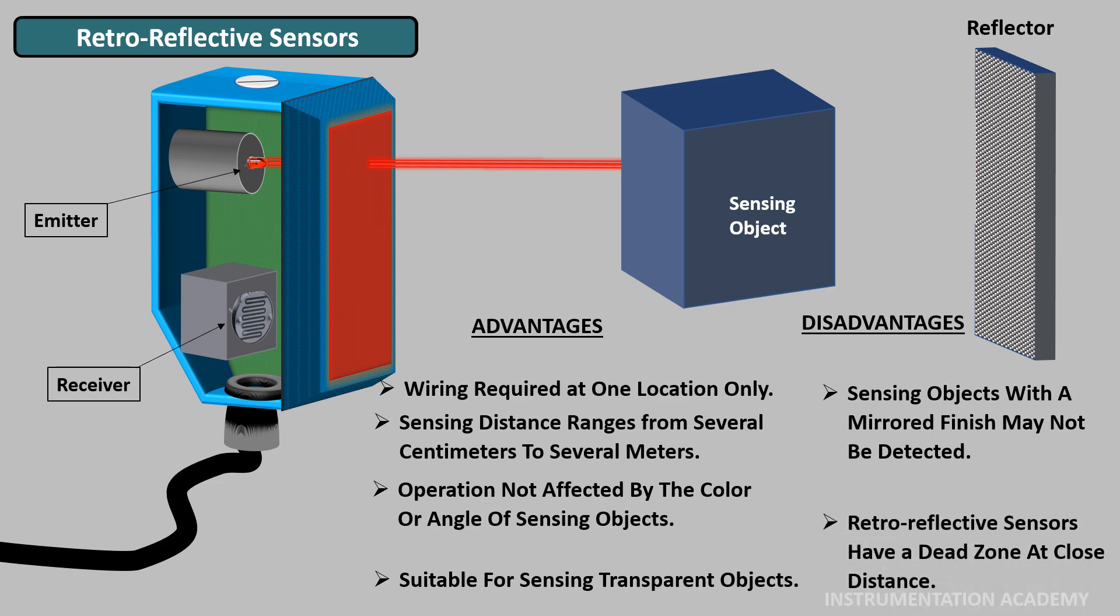Disadvantages of retro reflective sensors: Sensing objects with a mirrored finish may not be detected because the amount of light reflected back to the receiver from such shiny surfaces makes it appear as though no sensing object is present. Retro reflective sensors have a dead zone at close distance.